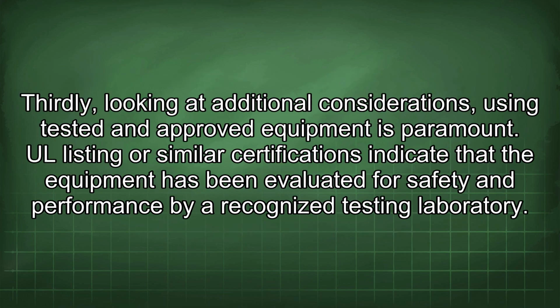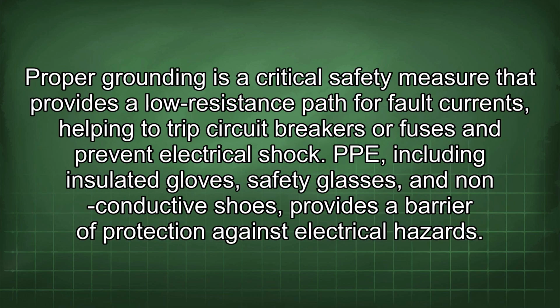Thirdly, looking at additional considerations, using tested and approved equipment is paramount. UL listing or similar certifications indicate that the equipment has been evaluated for safety and performance by a recognized testing laboratory. Proper grounding is a critical safety measure that provides a low resistance path for fault currents, helping to trip circuit breakers or fuses and prevent electrical shock.